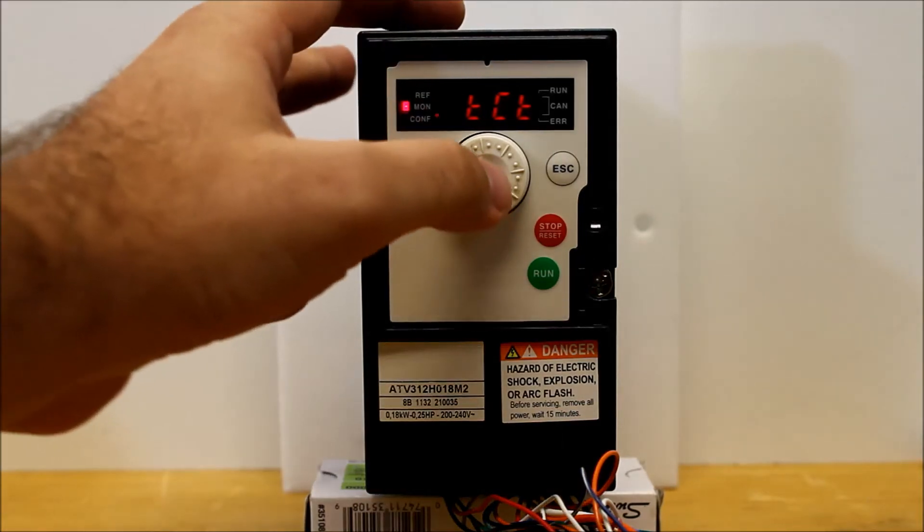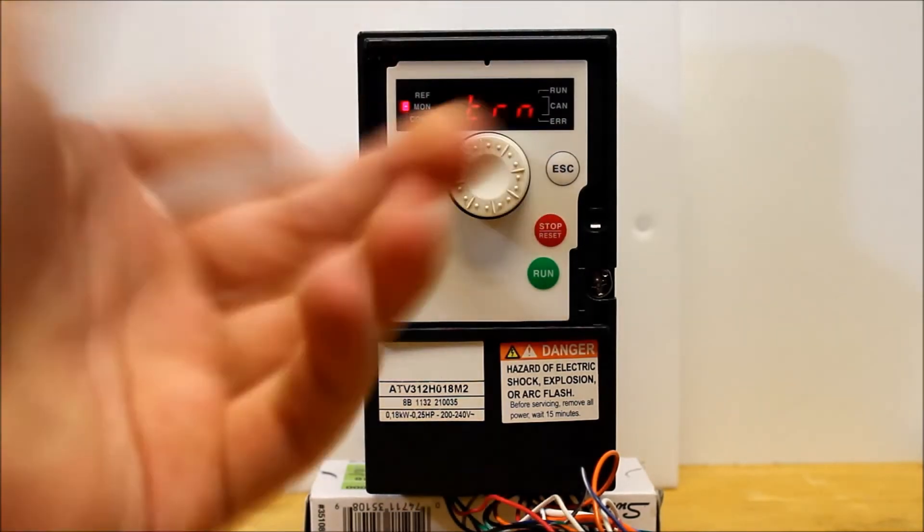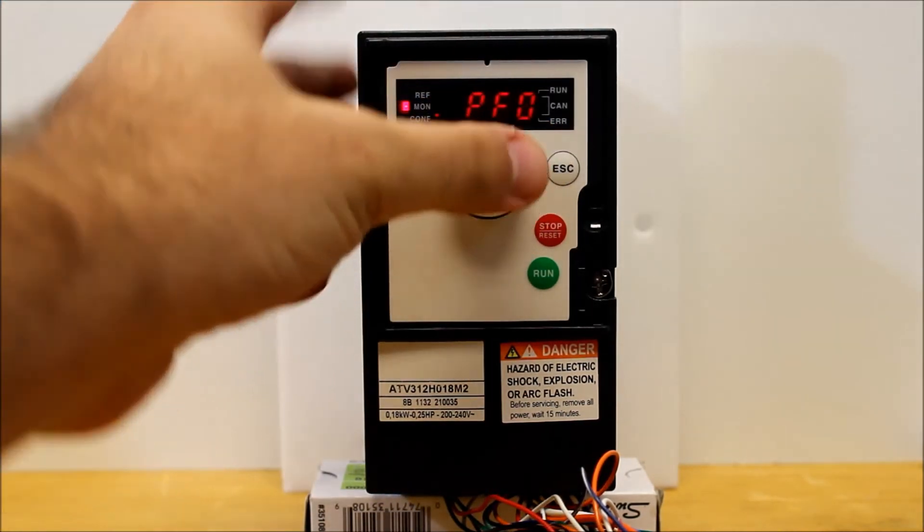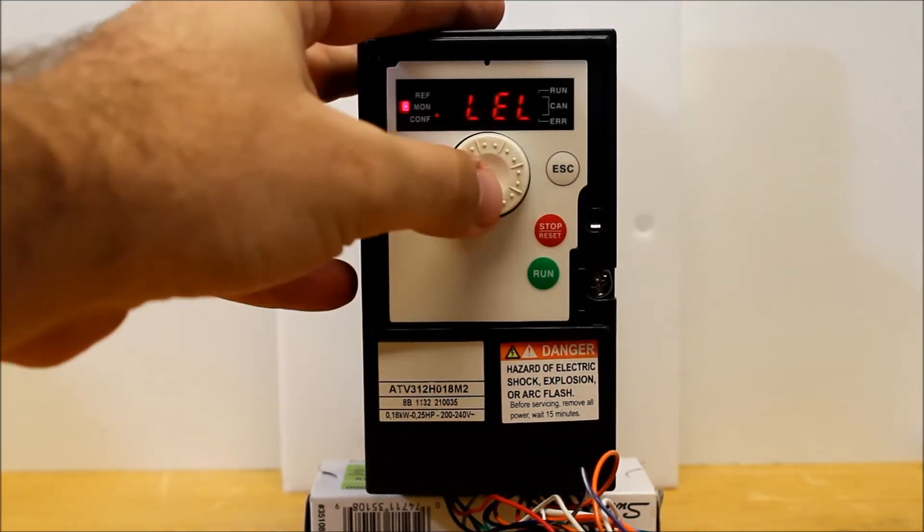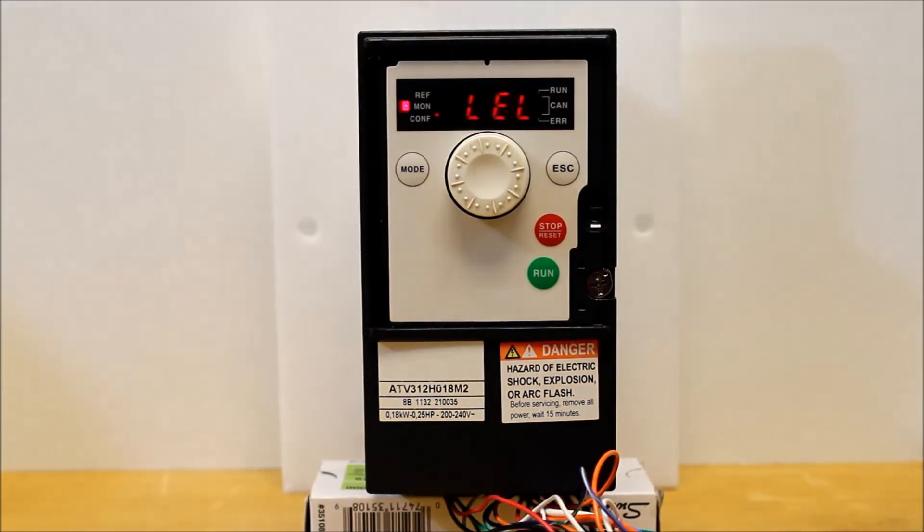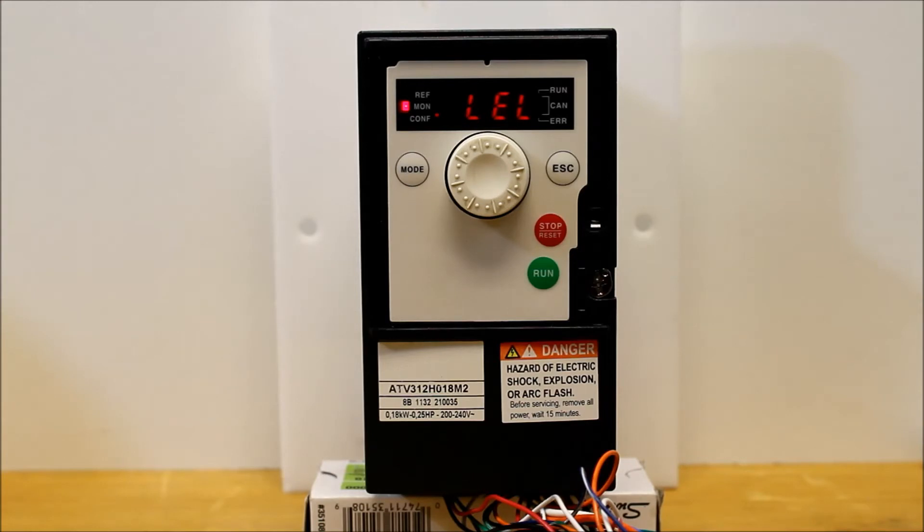But you can make it level control. So right now it's on transition. You can make it level, counterclockwise, enter on level. So what level means basically is that when the drive is powered up with a run command, it will just go ahead and run.